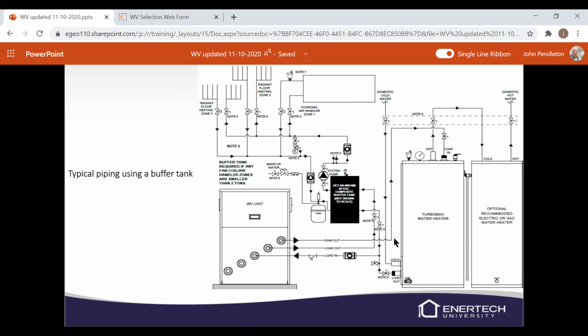You can kind of see here to the right that we have the TurboMax water heater and an optional or recommended electric or gas water heater for backup. If for some reason the load pump inside the WV unit fails, the homeowner has no hot water because we can't flow to the tank. So that becomes a real problem because, okay, they've been down for a day. You come out there and see it's a load pump. Well, now you've got to order a load pump. So you've got 3 or 4 days there where you're waiting on the part. So all that time, they're not going to have hot water. They're really not going to be happy about that.